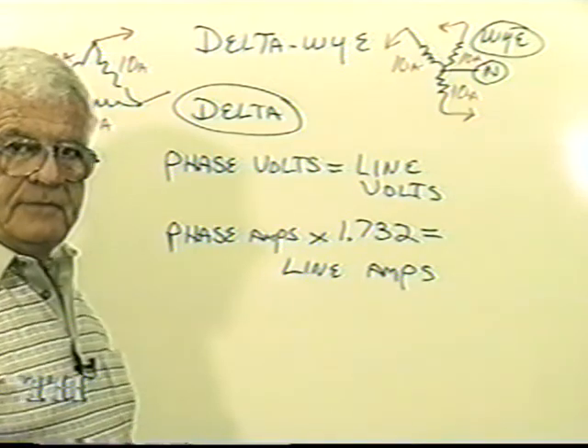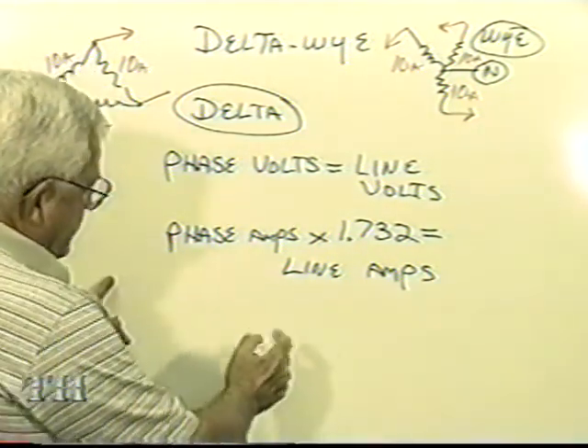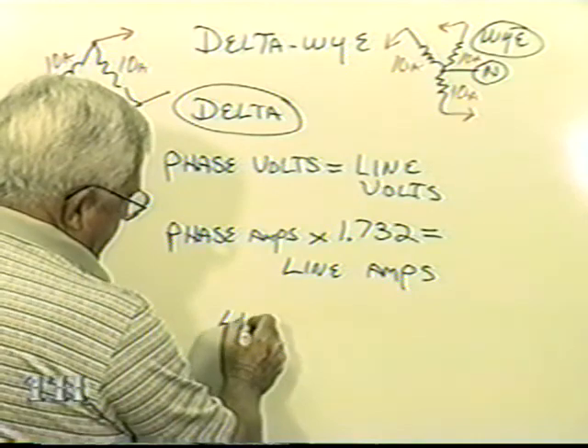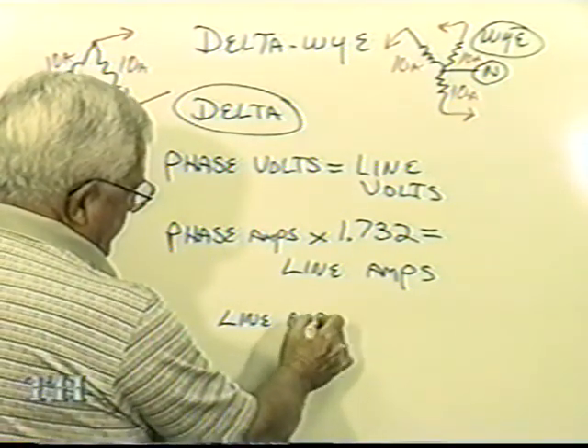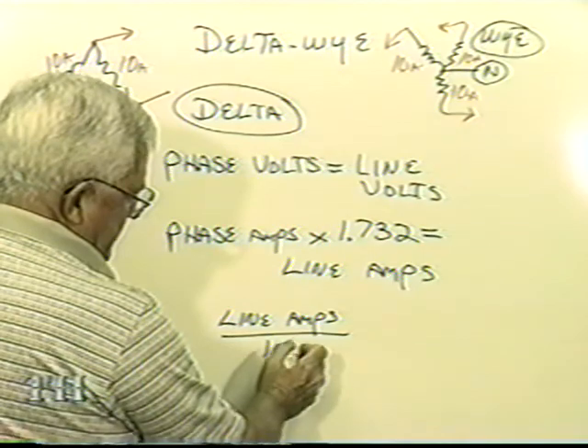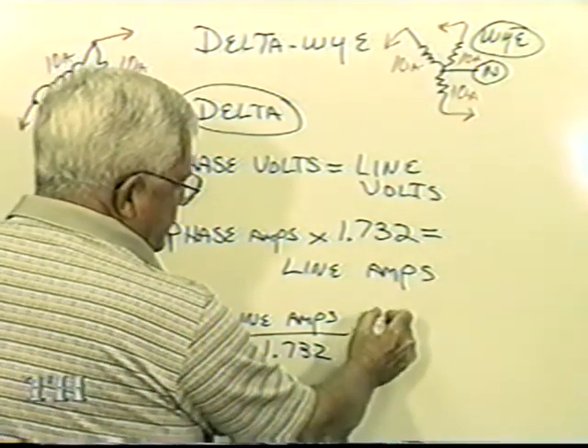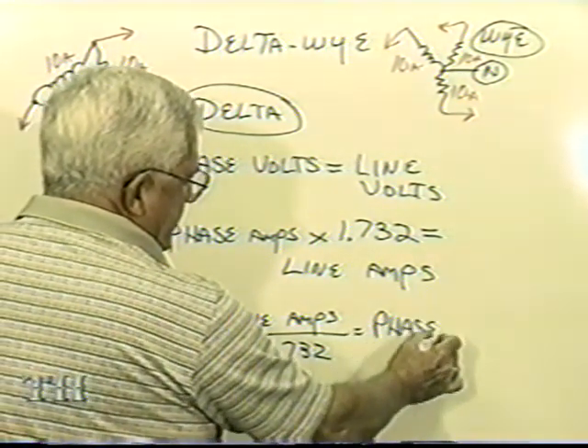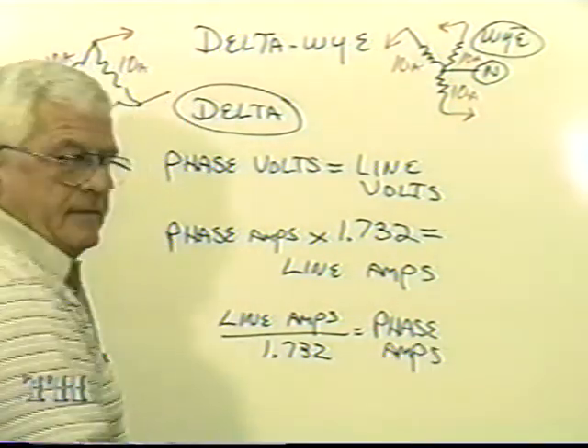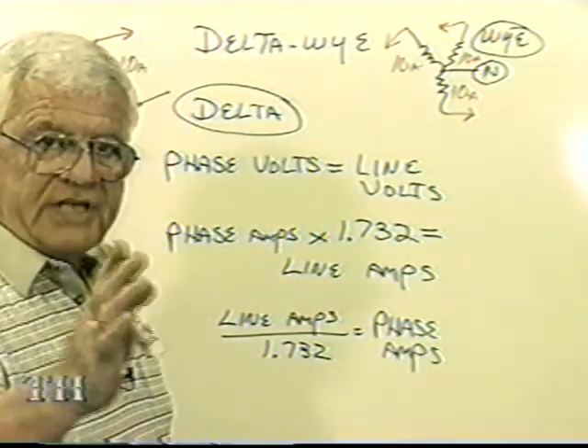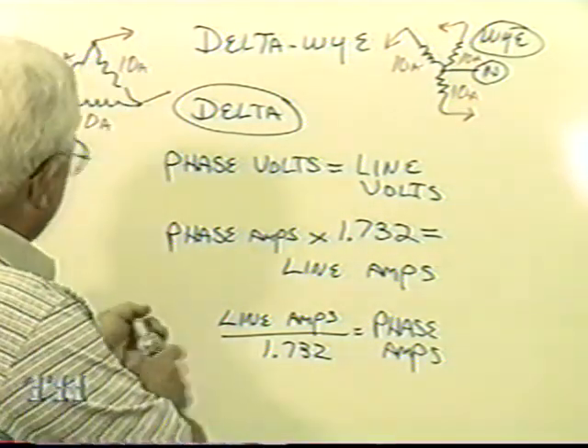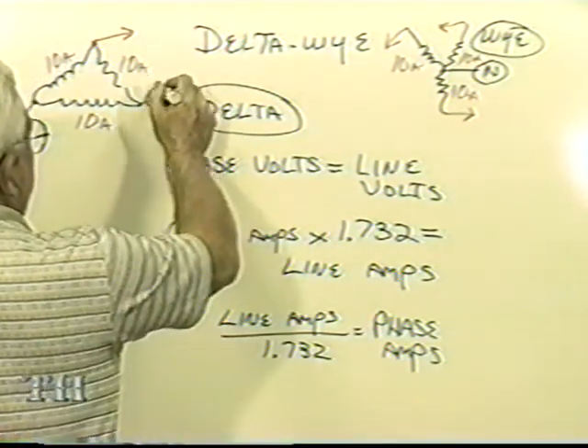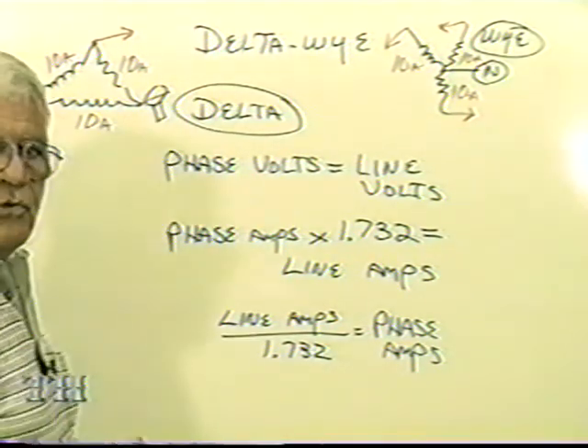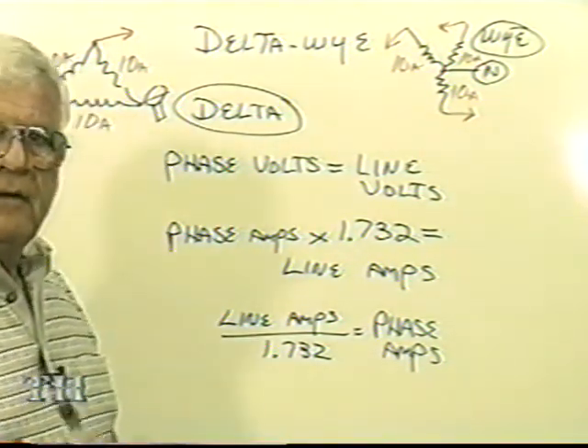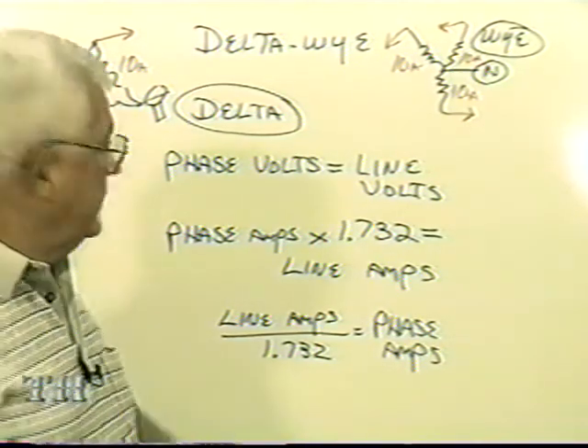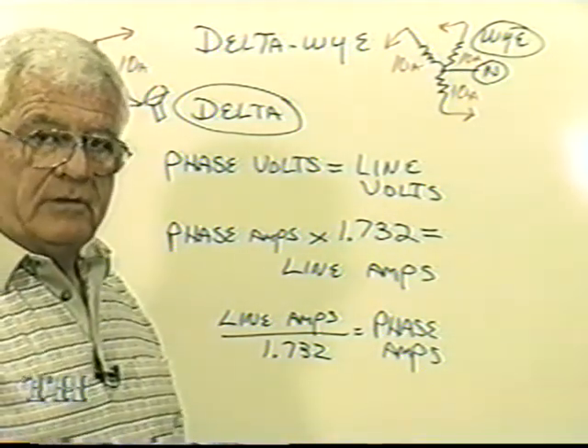Got one thing left to do in our format. For this delta, all you have to do is flip this over. Just take the line amps, divide that by the same number, the square root of 3, and it'll put you right back to phase amps. Example, say you're taking an exam, and they said, well, if you put an amp clamp right here, you put your old amp clamp right on that wire, what would that amp clamp be reading with a 3-phase 10 amp load? What?